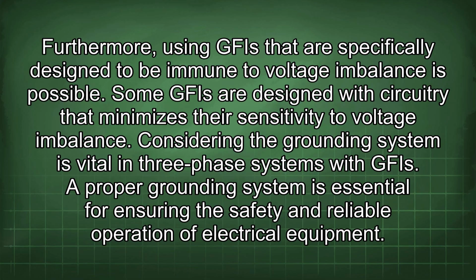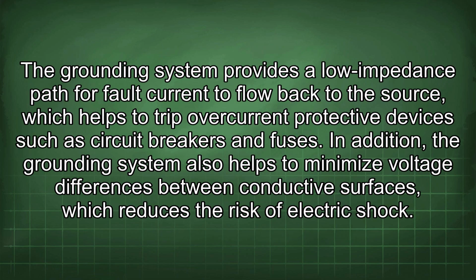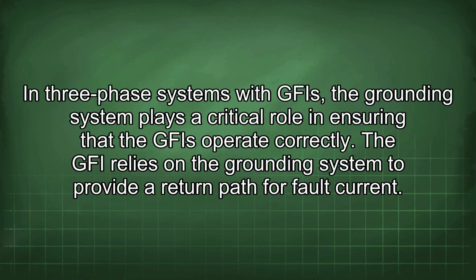Considering the grounding system is vital in three-phase systems with GFI. A proper grounding system is essential for ensuring the safety and reliable operation of electrical equipment. The grounding system provides a low impedance path for fault current to flow back to the source, which helps to trip overcurrent protective devices such as circuit breakers and fuses. In addition, the grounding system also helps to minimize voltage differences between conductive surfaces, which reduces the risk of electric shock. In three-phase systems with GFI, the grounding system plays a critical role in ensuring that the GFI operate correctly.